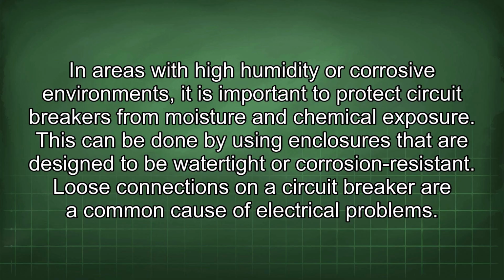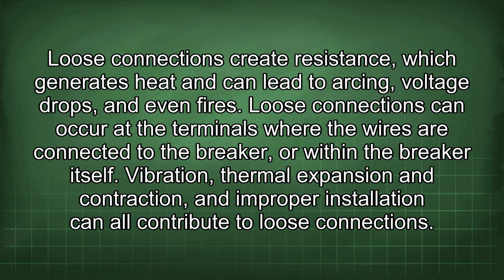Loose connections on a circuit breaker are a common cause of electrical problems. Loose connections create resistance, which generates heat and can lead to arcing, voltage drops, and even fires. Loose connections can occur at the terminals where the wires are connected to the breaker or within the breaker itself. Vibration, thermal expansion and contraction, and improper installation can all contribute to loose connections.